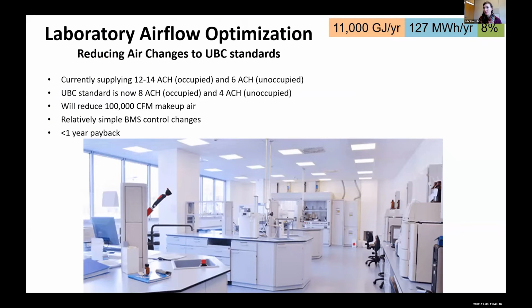At the same time, this building was an older building built in, I think, 2004, and it had fairly high air changes in the laboratories, roughly 12 to 14 air changes during the day, and 6 in unoccupied mode. And UBC implemented a new standard to have 8 and 4 occupied versus unoccupied. And we were able to adjust the air changes down from 12 and 6 to 8 and 4, reducing the amount of outdoor air in this building by roughly 100,000 CFM. This had a substantial impact on the energy use of the building, roughly 8%, and less than a 1-year payback because it took some engineering and controls changes by the BMS crew.